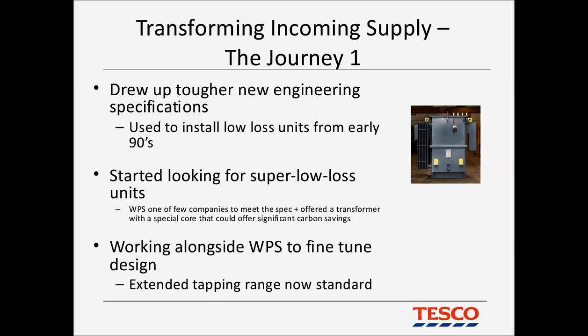A little bit of history now. Transformer history. Prior to 1990, we as a business did not have a defined engineering specification for transformers. We were predominantly led by the contractors, and they supplied, in essence, whatever they wanted in terms of product. We had no defined specification in terms of construction or losses. So, move forward to the early 1990s. We developed and introduced a specification, and as part of that specification we did dictate and state minimum core losses. These losses equated to somewhere between standard and low loss in terms of current day technology.